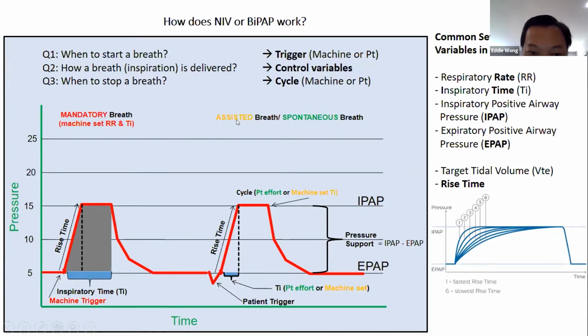So if you use ST mode, then you have the mandatory breath and the spontaneous breath. If you use the pressure control mode, then you have the mandatory breath and assisted breath, which allows the patient to trigger the breath by their own, which means even though your rate setting is 10, are you allowed to trigger the 11th breath, the 12th breath, the 13th breath, 14th breath? The answer is yes, because the mode you selected consists of either assisted breath or spontaneous breath under ST mode or pressure control mode. So you are allowed to have additional breath support by the machine. But how long this air can sustain during inhalation depends whether it follows the I time or follows the patient effort, spontaneous effort. Okay.